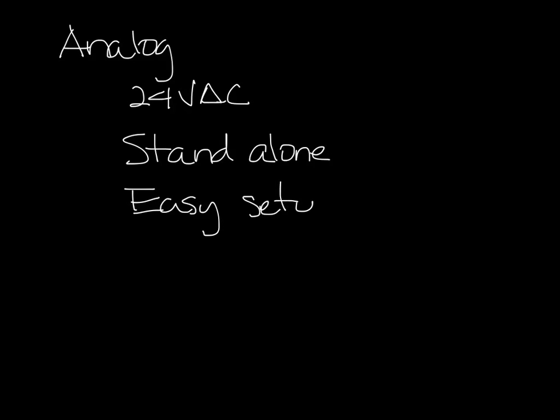Next we have analog controls, also known as analog electronic controls. They're a 24VAC controller, and they operate in a standalone configuration only. They have very easy setup using just the thermostat to set up your CFM and all the parameters you need.